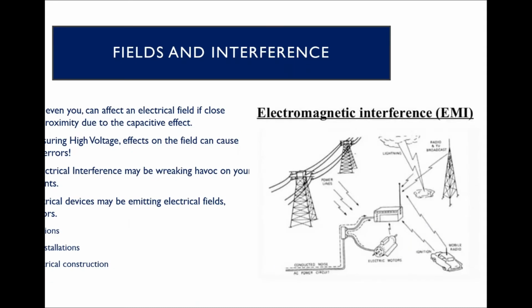So moving on, with the higher voltages, larger electrical fields are generated, and typically all the equipment used is also a lot larger. So depending on your measurement technique, these can be really heavily influenced to cause error in your measurement. Many of these are predominantly AC specific, but DC measurements can still be affected in some techniques. So really any object, even your own body, can affect an electrical field if close enough in proximity to it due to a capacitive effect. So basically, if you are standing 1 foot away from your high voltage source, you're going to cause an effect to it that would be different than if you were standing 5 feet away, as your body acts as some capacitive effect to the field, and it's going to alter your measurements.